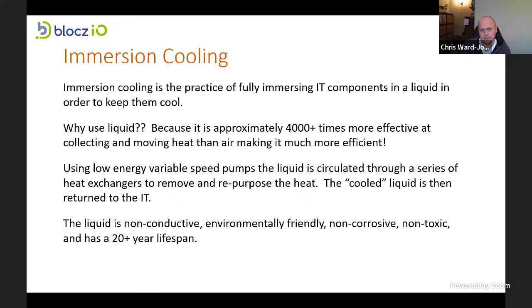We use a dielectric liquid, others use or have been using oil. If you look back through time, old mainframe computers used a very similar approach, cycling oil through their components. But there are implications with using oil - environmental impact, it doesn't last very long so you have to dispose of it, and it has a flash point, so there's fire risk. There are pros and cons to that approach. Dielectric fluid, on the other hand, is non-corrosive, non-toxic, and has a 20-year lifespan. You can drink it if you want - I've tried it, it doesn't taste very nice, so I don't really recommend it.